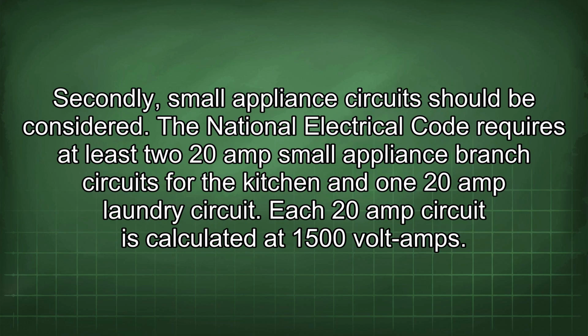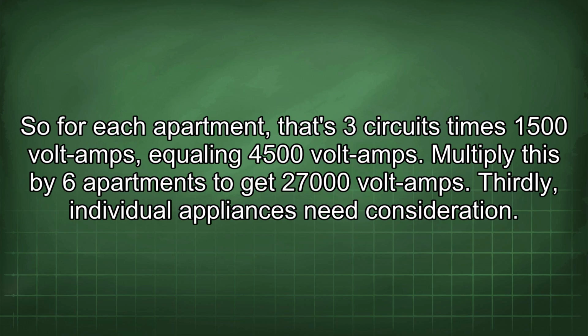Secondly, small appliance circuits should be considered. The National Electrical Code requires at least 2 20-amp small appliance branch circuits for the kitchen and 1 20-amp laundry circuit. Each 20-amp circuit is calculated at 1500 volt amps. So for each apartment, that's 3 circuits times 1500 volt amps, equaling 4500 volt amps. Multiply this by 6 apartments to get 27,000 volt amps.